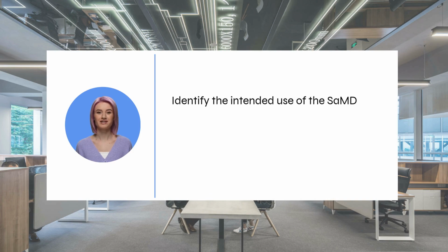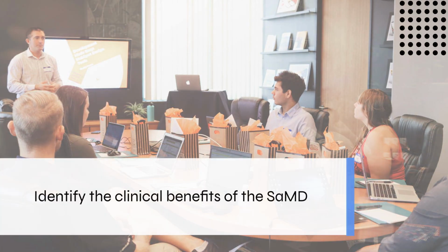The first step in SaMD clinical evaluation is to identify the intended use of the software. This involves defining the medical condition that the software is intended to diagnose, treat, or prevent, as well as the patient population for which the software is intended. The next step is to identify the clinical benefits of the SaMD. This involves determining how the software will improve clinical outcomes. Some examples would be improving patient outcomes, reducing the risk of adverse events, or increasing efficiency in the clinical setting.